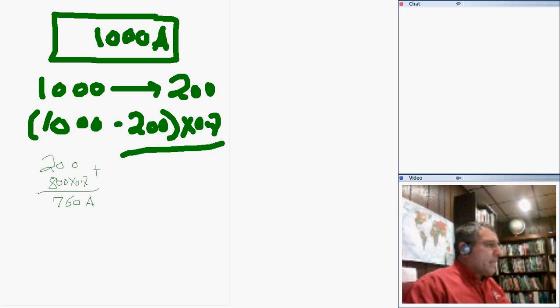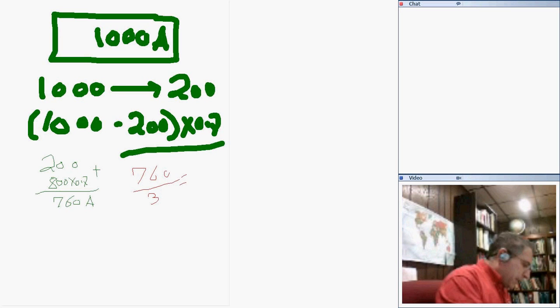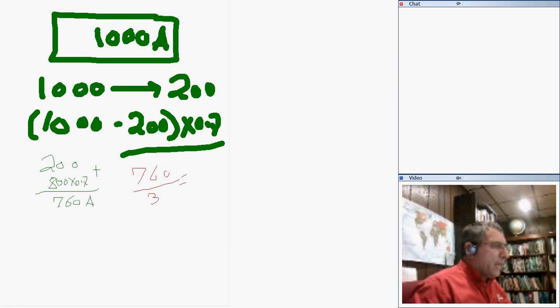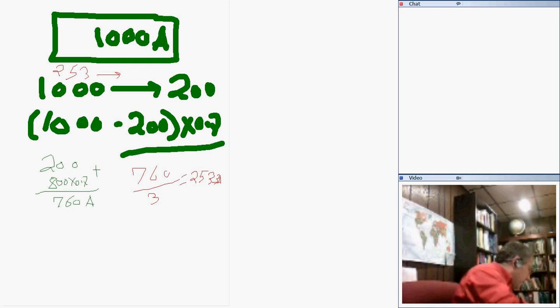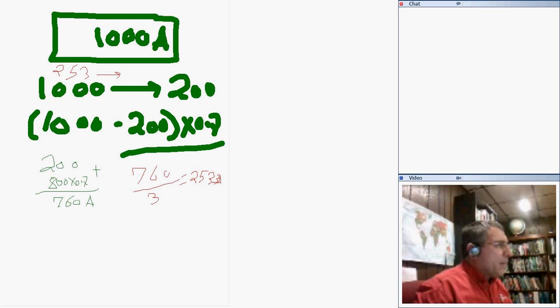Now I take this 760 amps and divide by 3, because I parallel 3. If we divide by 3, we get 253.3 amps. Perfect, no problem. Then take my 253 amps and go to Table 310.16. 253, that's 250, so get me one conductor. Remember, it's a neutral only conductor: 250 kcmil.